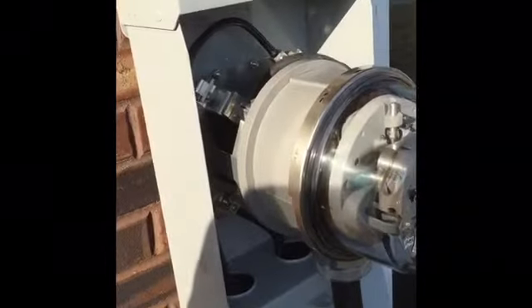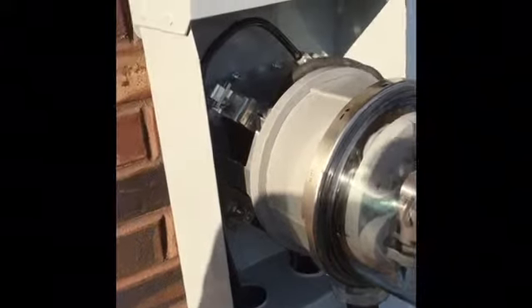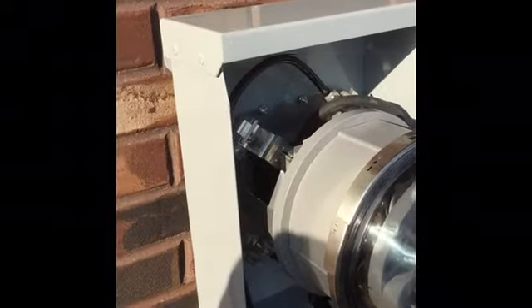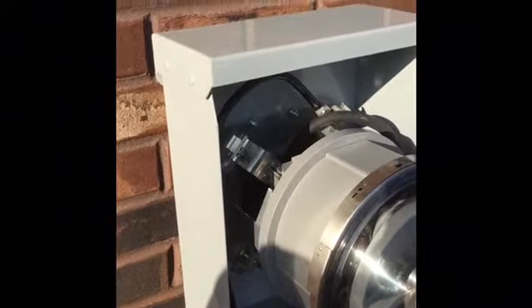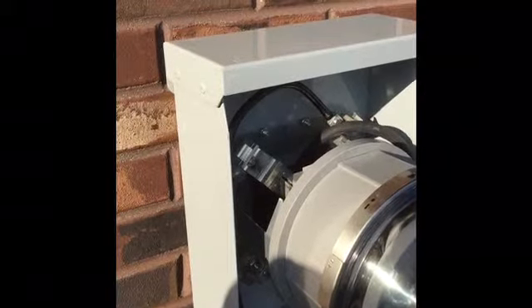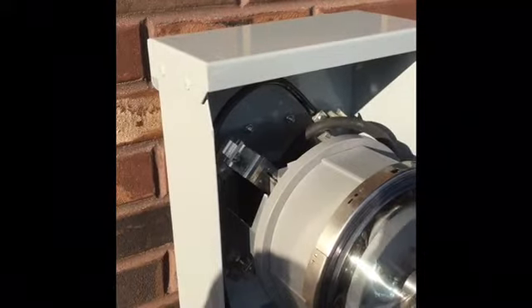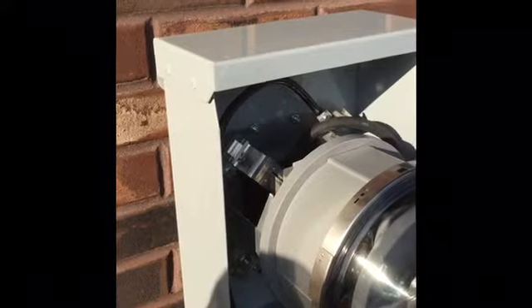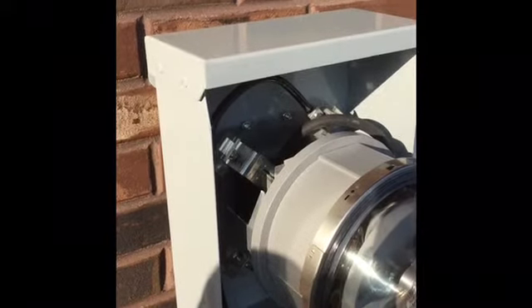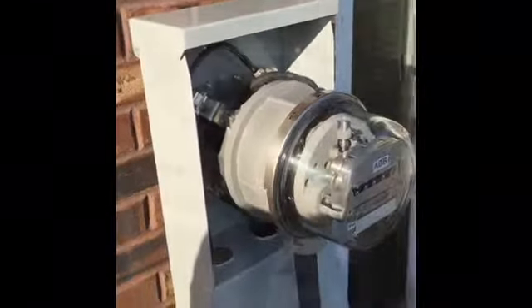Okay, and then we test for the voltage on the top side, the line side of the meter socket there, and check to see if we have 120/240. And as long as we do, everything looks good. Go inside, turn the customer's breaker on.